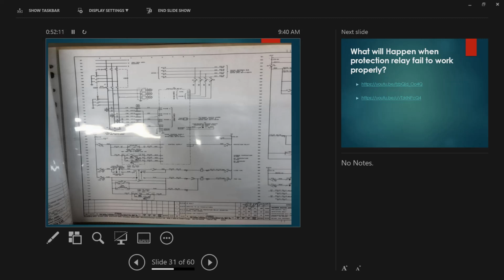Yeah. So what? And they didn't believe me again. Like, no, it's already done in commissioning. But I need to get your permission if there's something wrong. So that's why documentation is very important, even though it takes a while to do relay testing. It's not like a breaker that you just connect your cable, that's it. Relay testing needs you to have good experience and knowledge on what you're doing.